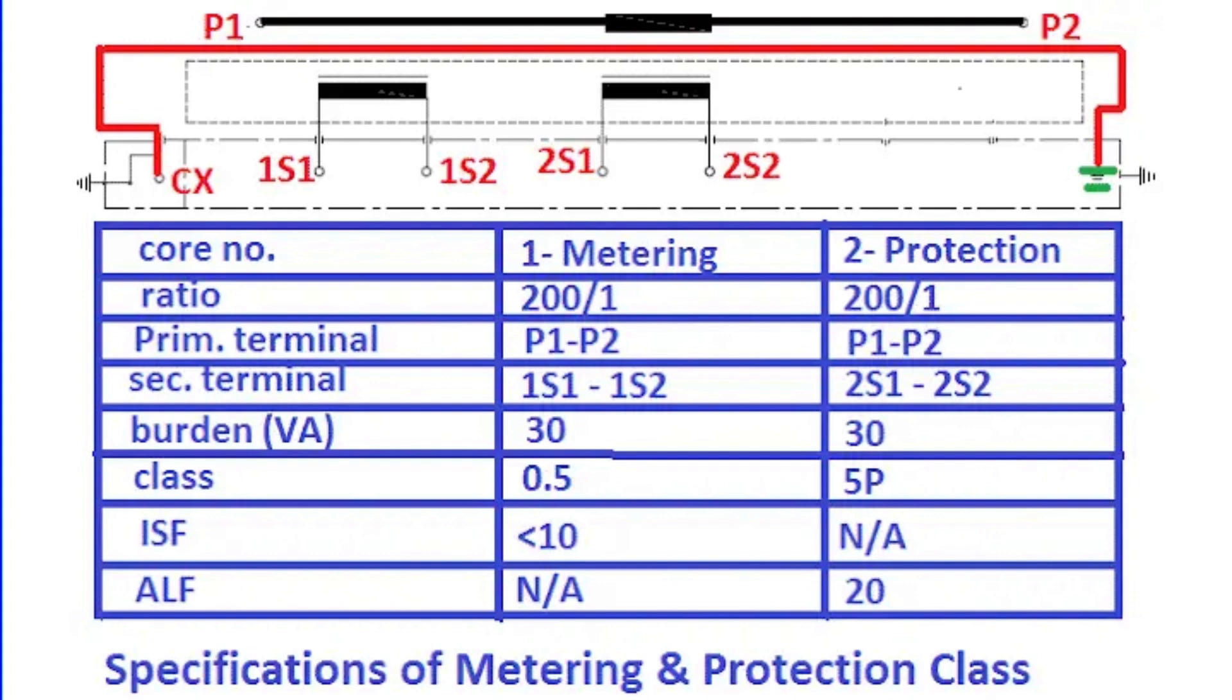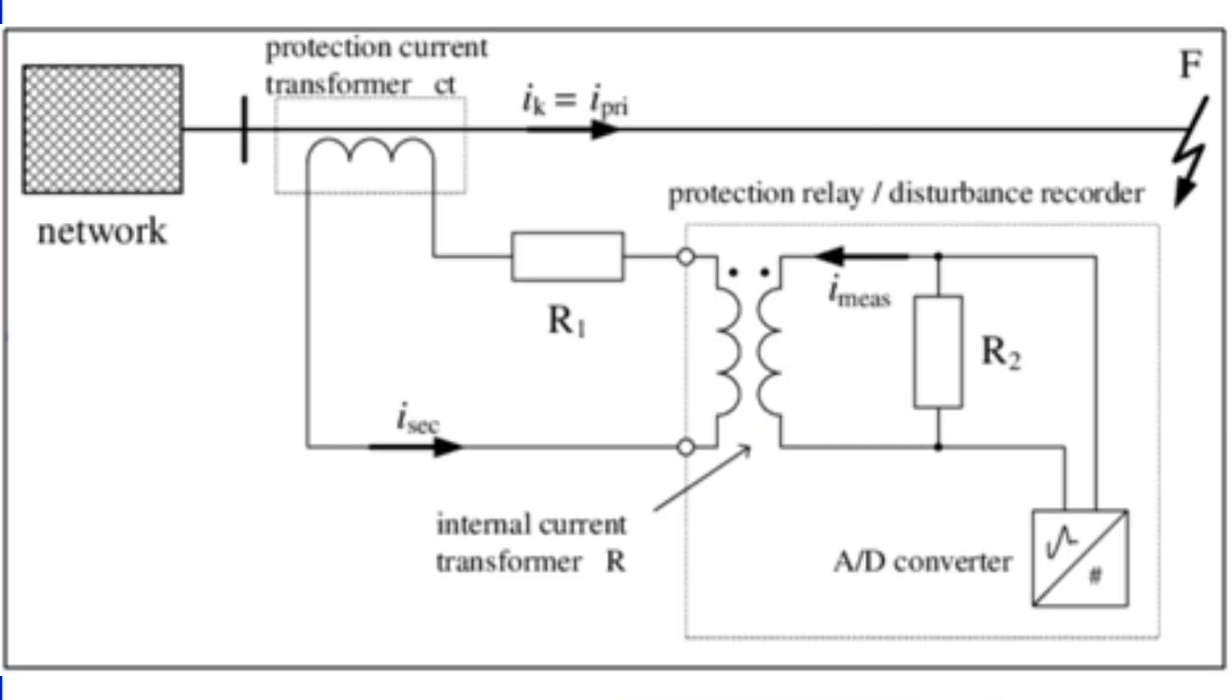Let's discuss why. Protection CTs are designed to measure fault currents that are 10 to 20 times the rated current. Their primary job is to send accurate inputs to relays during fault conditions. The relay then decides whether to send a trip signal to isolate the faulty section.